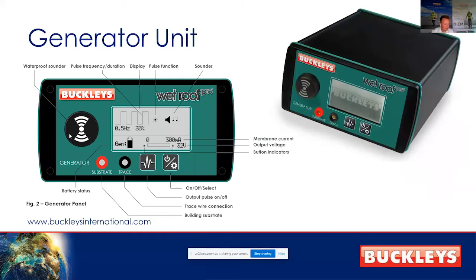The generator, a little like the dry kit, shows an amount of current on the machine - this is in milliamps rather than microamps on the dry kit. When you set the machine up, you'll see this little bar go across the screen back and forward as the voltage is pulsed onto the membrane.